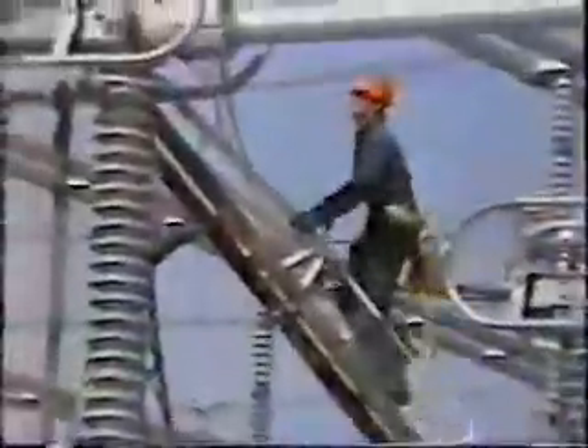As several different groups are working around the equipment, it is essential that all safety rules and procedures be strictly observed. The work should be performed under any necessary permits required, typically a permit to work or a permit to test. All documentation and report forms must be ready, as it is essential to keep accurate records of all tests and operations. The recorded figures provide a benchmark for comparison of future routine test results. This information could also provide the basis of a claim against manufacturers or contractors in the event of unacceptable work. It could also be used in testimony before a utility commission or in court.